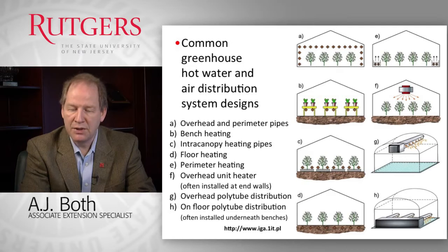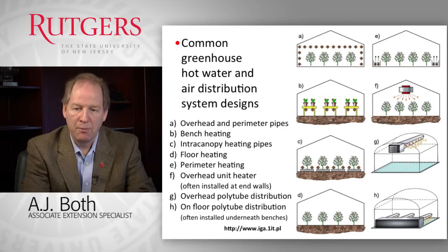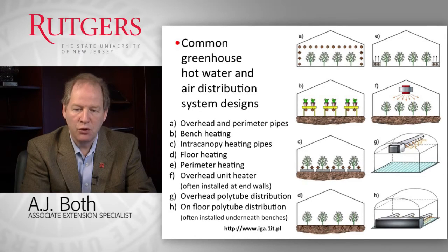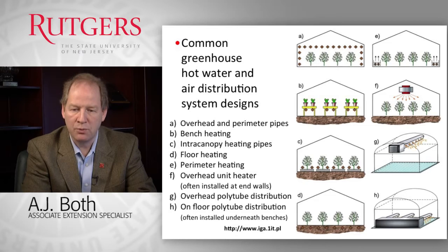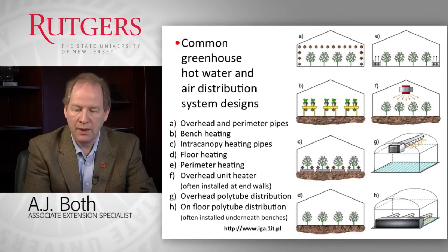We can have overhead unit heaters, sometimes operated by steam but typically by hot water, very often installed along the end walls that blow jets of warm air throughout the greenhouse environment. To improve the distribution of warm air, we can attach a polytube to the outlet of one of those unit heaters. Air comes out small holes all along the length of the polytube, distributing heat more uniformly. Those polytubes can be installed overhead or, when space allows, underneath the benches.